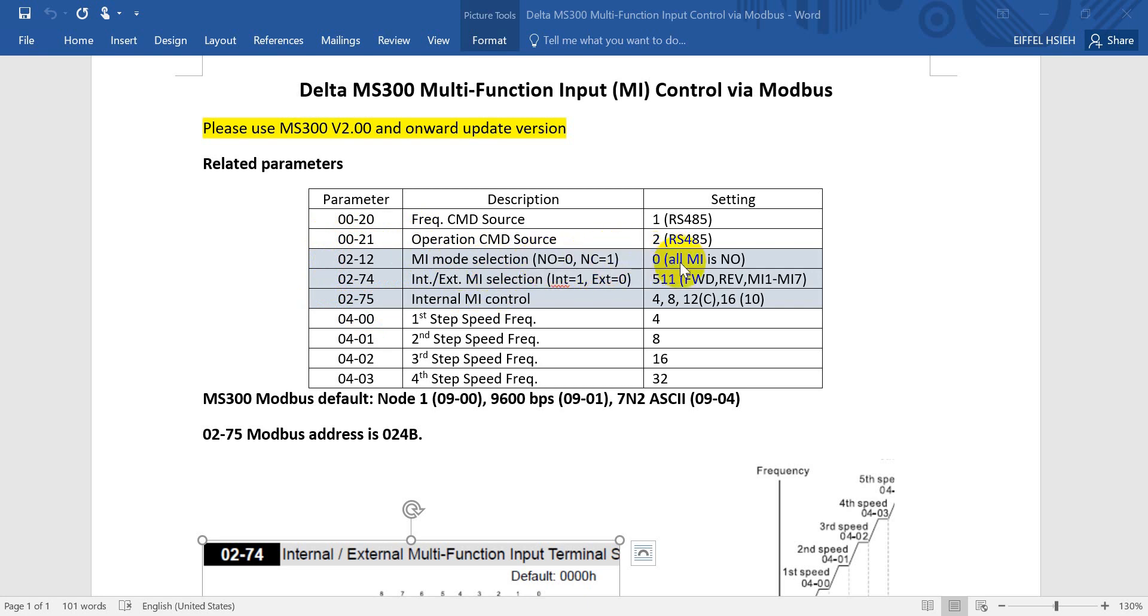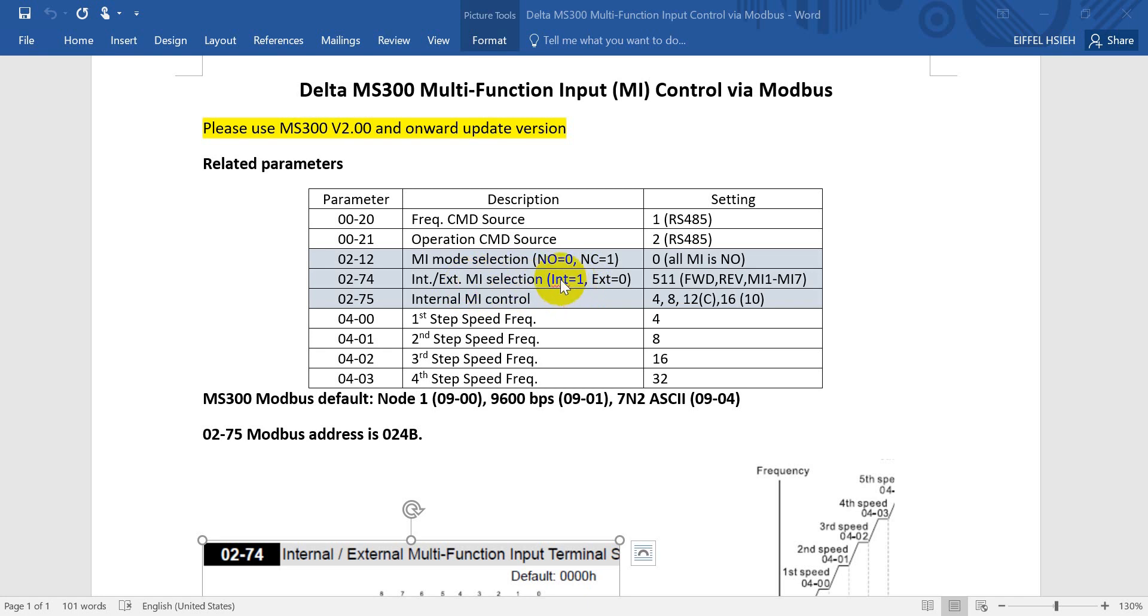P02-12, P02-74, and P02-75. P02-12 defines whether the digital input works as normally open or normally closed. The default setting is zero, that means all the multi-function inputs or digital inputs are normally open. P02-74 defines the internal and external selection. If you use 1, that means you define this MI as internal.